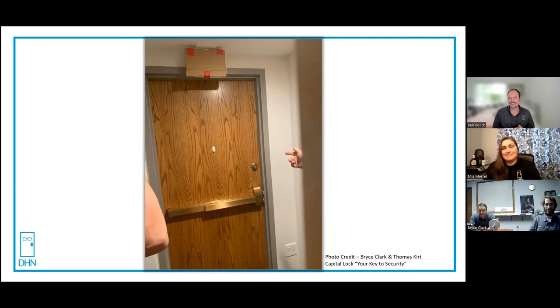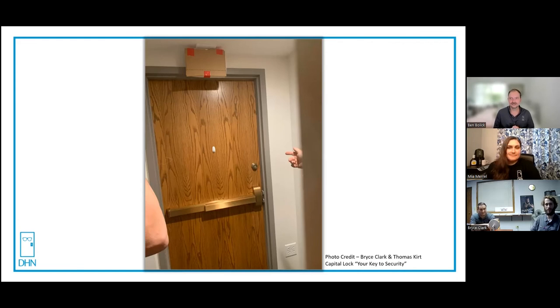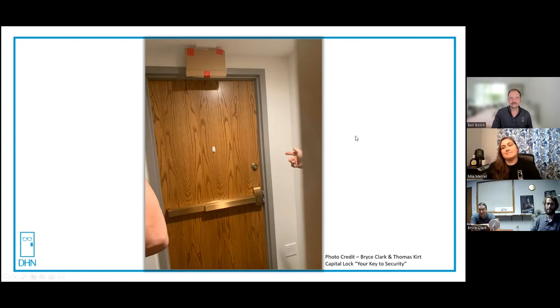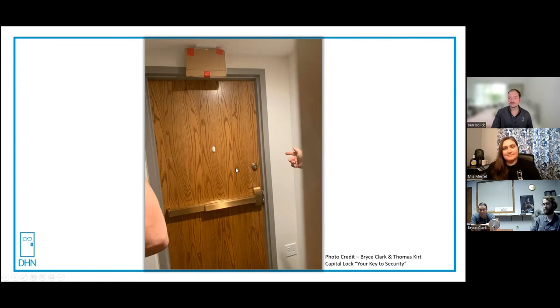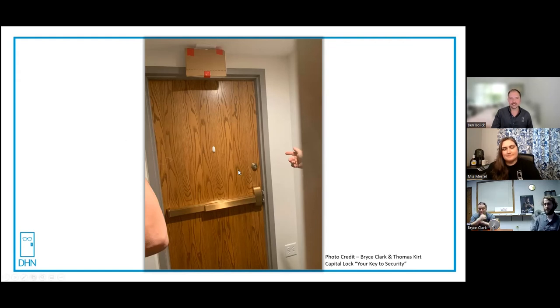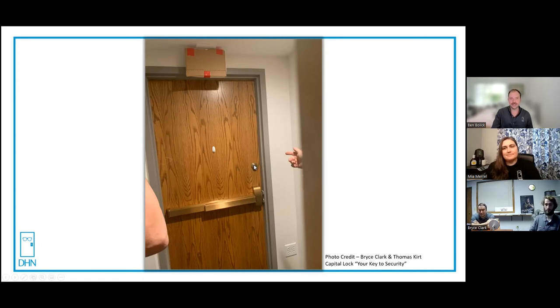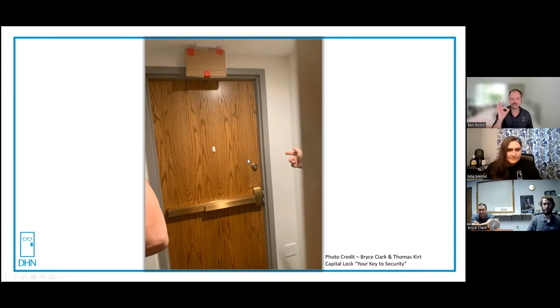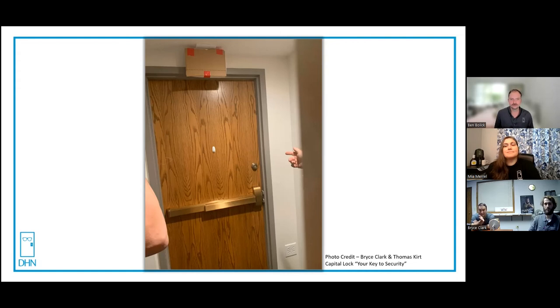Yeah. Unfortunately, it's probably something you're just going to have to replace the whole door and frame. I mean, you could potentially fill it. That's a tough one. Yeah. Bryce is now certified as a fire door inspector. So, we were kind of looking to devise a plan of, okay, can we salvage this door? Is there a proper way we can do this where it is still going to be a fire door? But unfortunately, I think we are going to have to order a new door for this one. Yeah. I think at least it's going to have to get recertified because once you remove that deadbolt, you're losing a lot of the integrity of that fire door. And that's going to be a penetration point for fire and smoke. I can't tell what kind of deadbolt it is. It's larger than an inch cutout. And that's the whole thing. It is a Kwikset. So, I believe that was, what, inch and an eighth. So, it's already more than the inch. So, yeah.